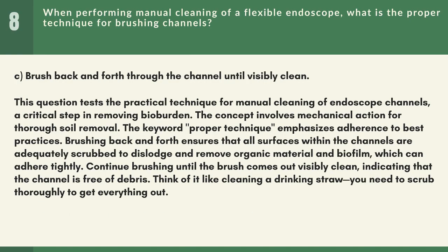Answer: C. Brush back and forth through the channel until visibly clean. This question tests the practical technique for manual cleaning of endoscope channels, a critical step in removing bioburden. The concept involves mechanical action for thorough soil removal. The keyword proper technique emphasizes adherence to best practices. Brushing back and forth ensures that all surfaces within the channels are adequately scrubbed to dislodge and remove organic material and biofilm, which can adhere tightly. Continue brushing until the brush comes out visibly clean, indicating that the channel is free of debris. Think of it like cleaning a drinking straw. You need to scrub thoroughly to get everything out.